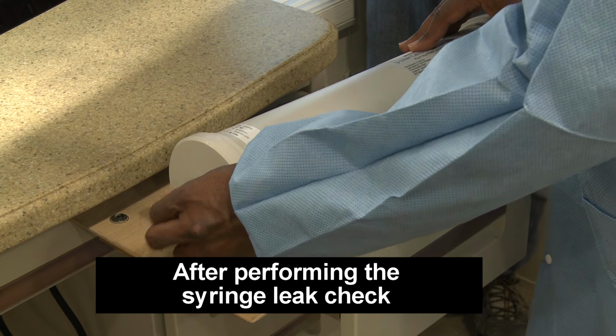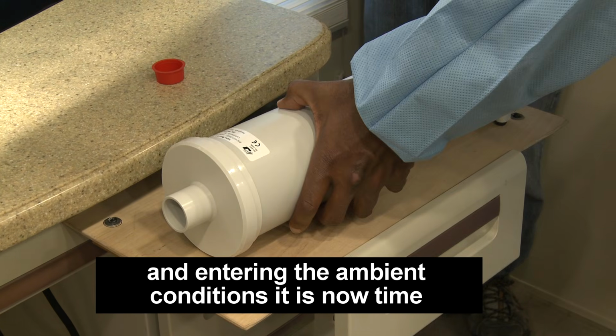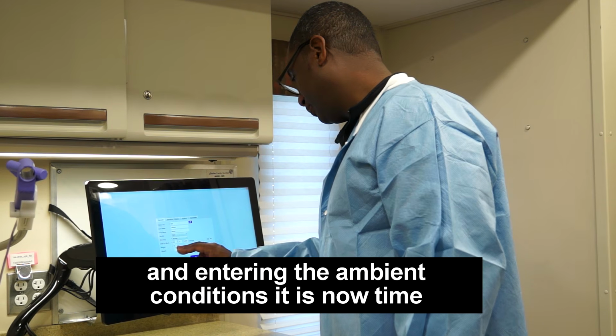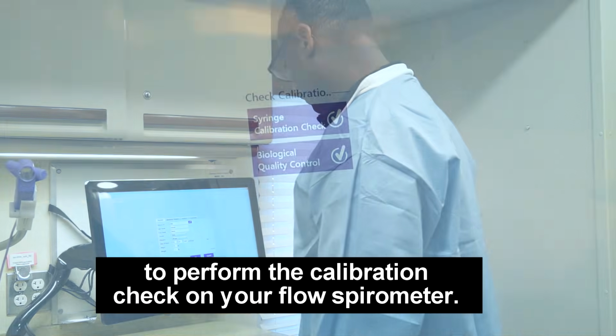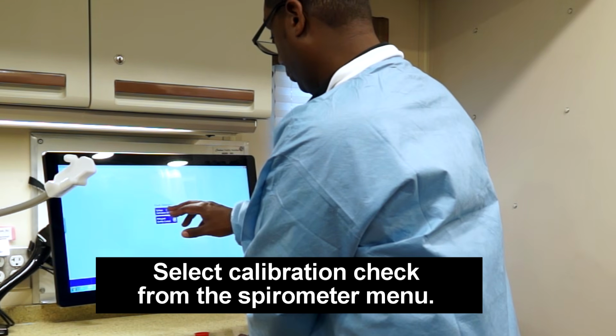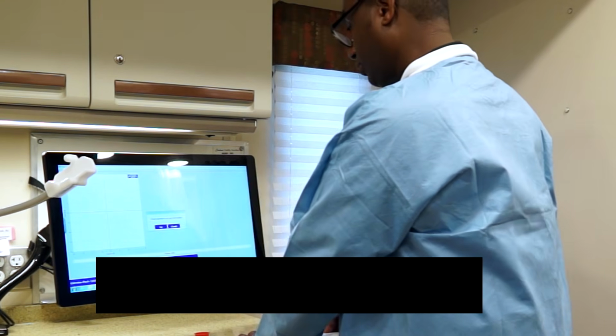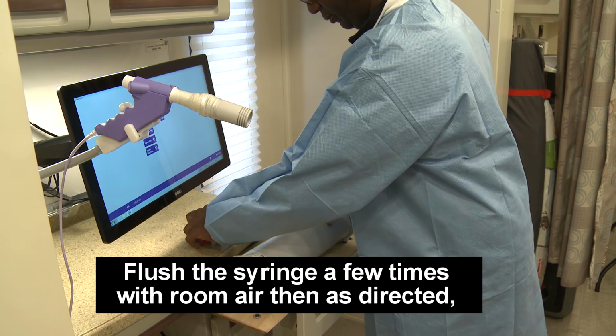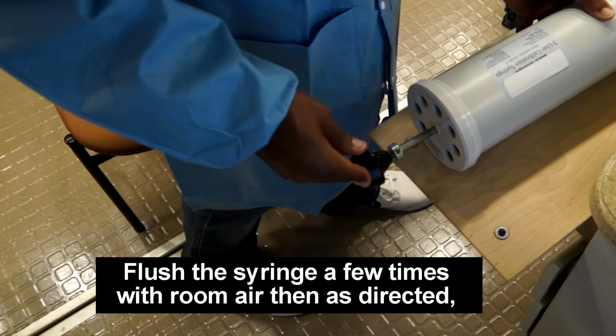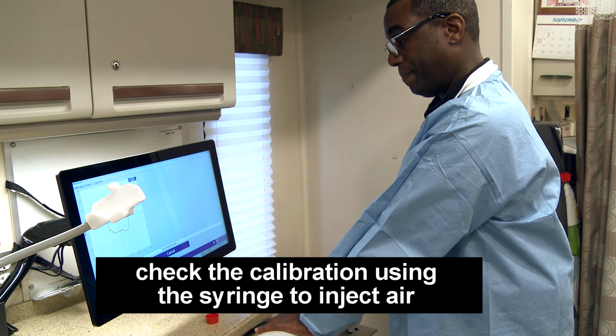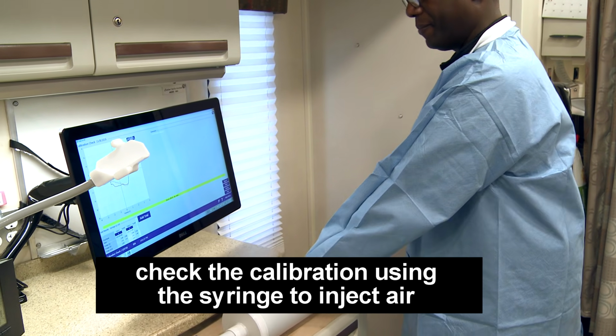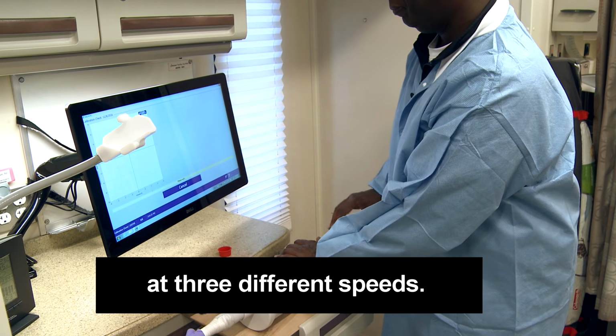After performing the syringe leak check and entering the ambient conditions, it is now time to perform the calibration check on your flow spirometer. Select Calibration Check from the spirometer menu. Flush the syringe a few times with room air. Then, as directed, check the calibration using the syringe to inject air at 3 different speeds.